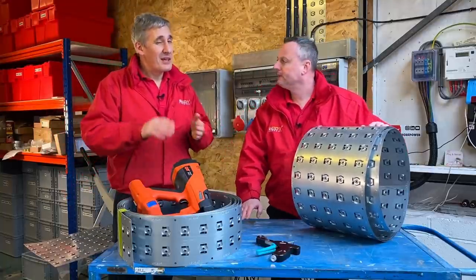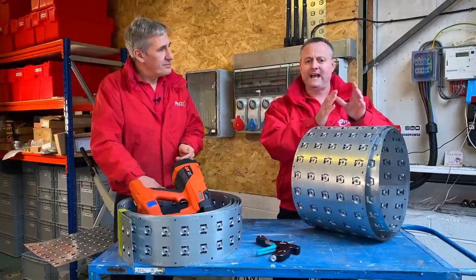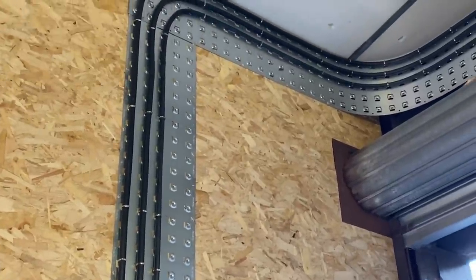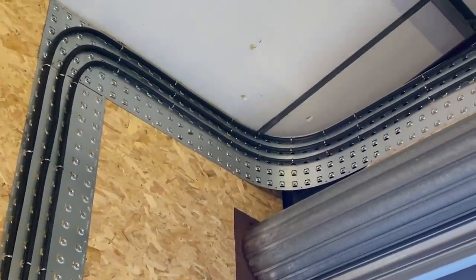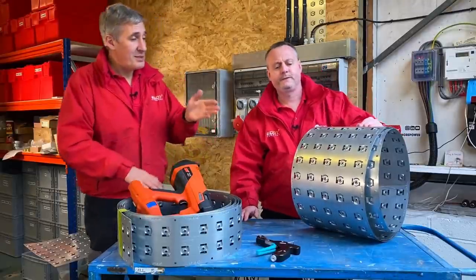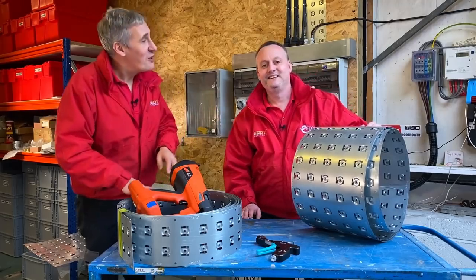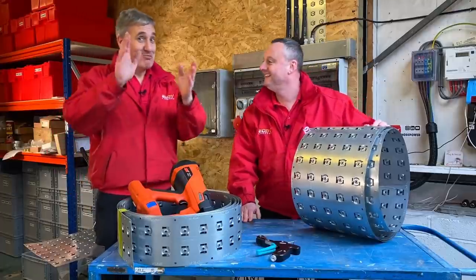It's 0.8 of a millimeter in thickness and comes in three standard widths: 300, 450, and the smallest at 150mm. In this job we've used the 300 and the 150. It has to be a surface that's smooth and flat - you're not going to hang it from a trapeze on the roof or set it over girders, as it is designed for flat surfaces.